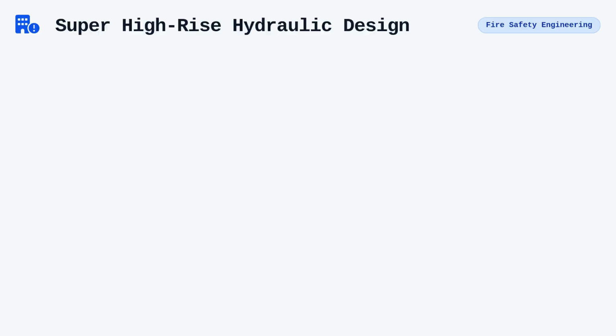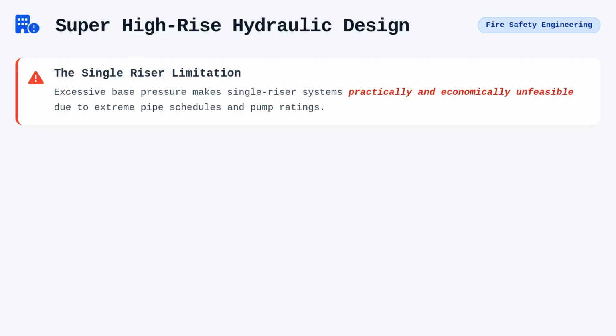In dealing with super high-rise buildings, the complexity increases logarithmically due to the need for multiple pressure zones and express mains. A single riser column cannot service a skyscraper because the pressure demand at the base would necessitate pipe schedules and pump ratings that are practically and economically unfeasible.